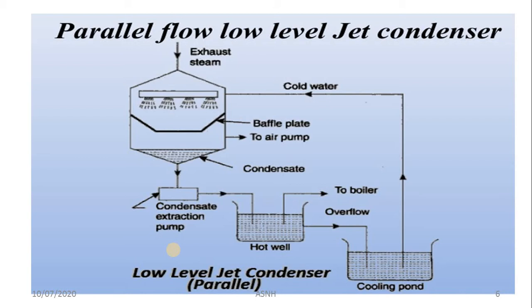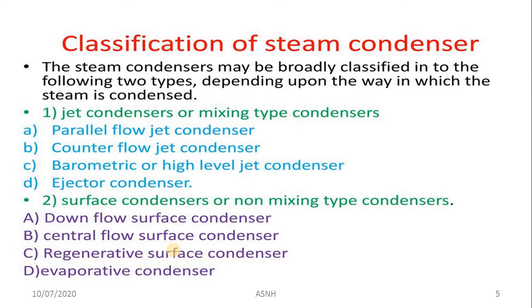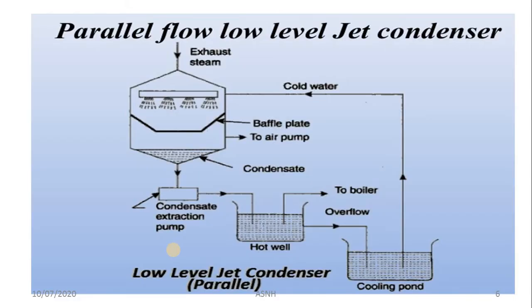So students, keep in mind that the jet condenser is classified into two types: low level jet condenser and high level jet condenser. In the case of the low level, a condensate extraction pump is mandatory, but in the case of the high level condenser, the condensate extraction pump is not required. So parallel flow and counter flow jet condensers come under the low level condenser, and the barometric and ejector type condensers come under the high level jet condenser, where there is no requirement of a condensate extraction pump to move the condensate into the hot well.